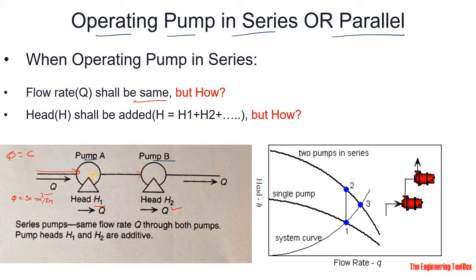When both pumps are in series, the flow rate will be the same because the outlet of pump A becomes the inlet of pump B. However, the heads are different — H1 and H2 — so the head will be additive: total head equals H1 plus H2. If there are more pumps, they also add. This is what you see in multi-stage pumps, such as a boiler feed pump.